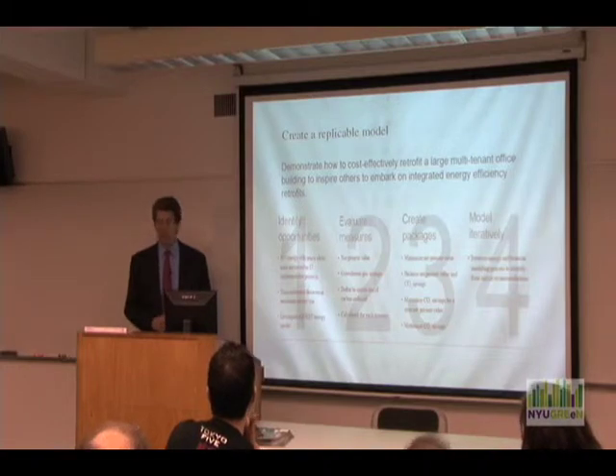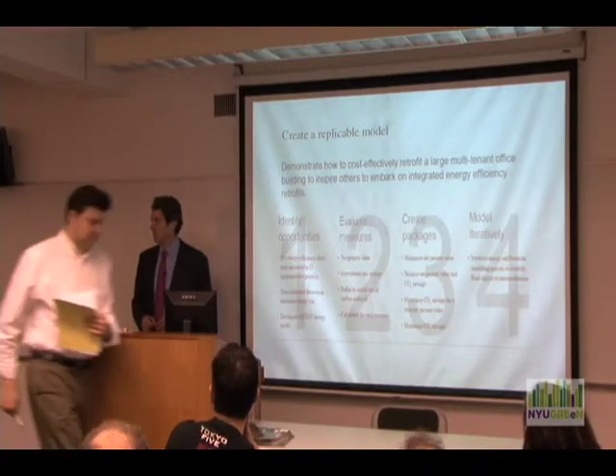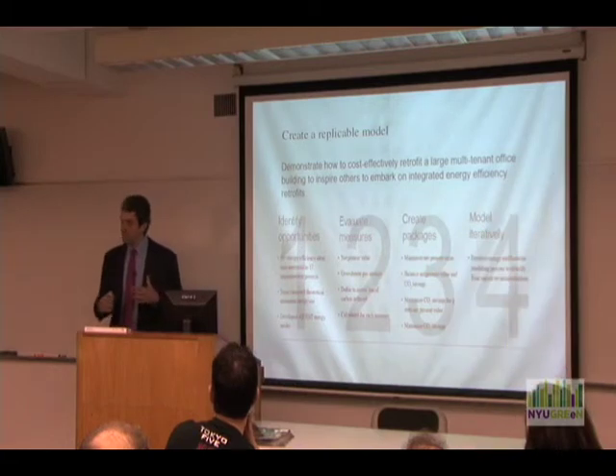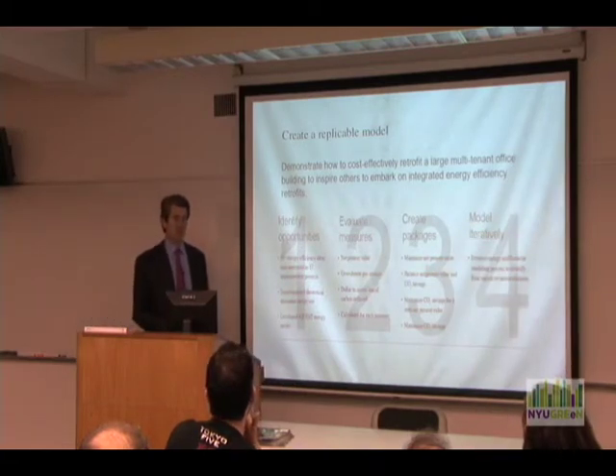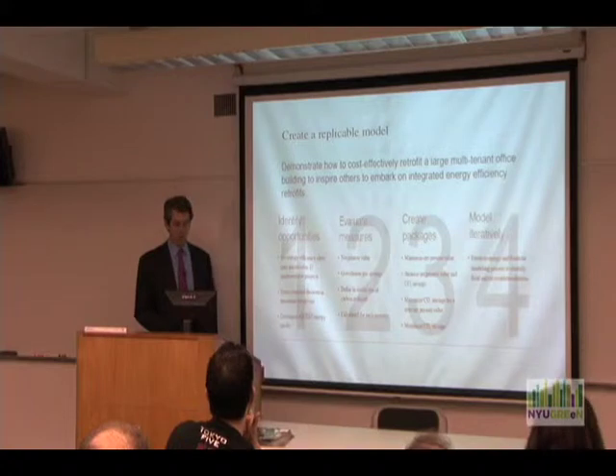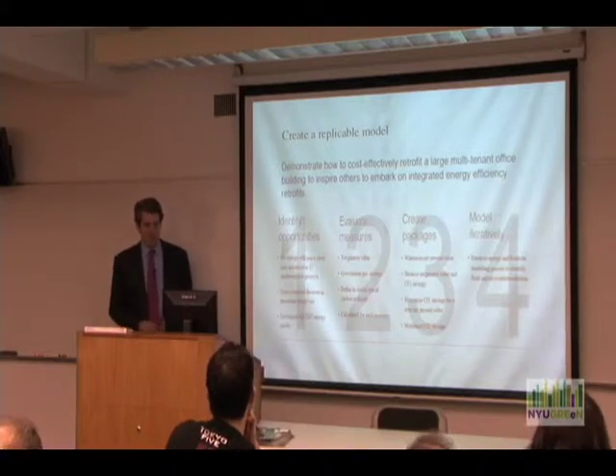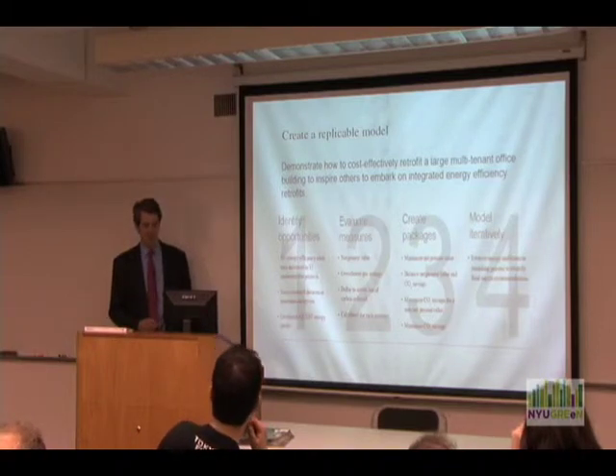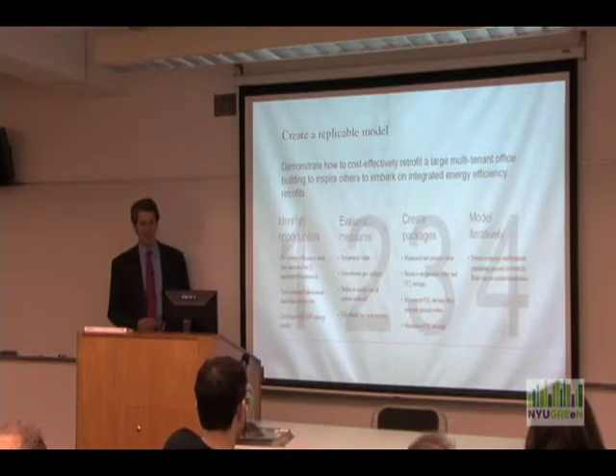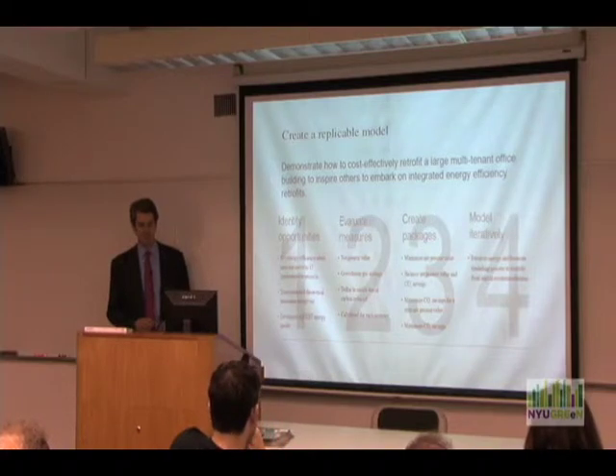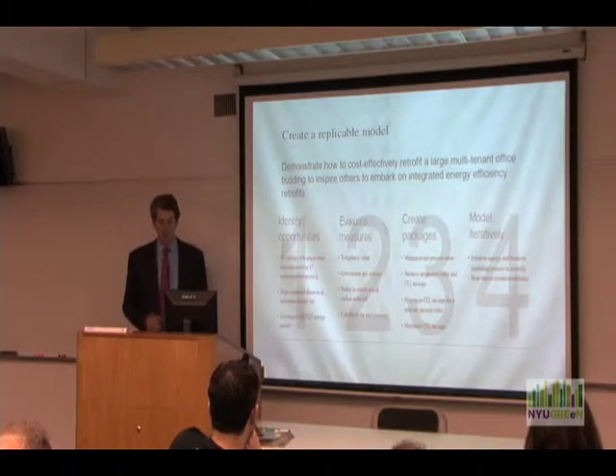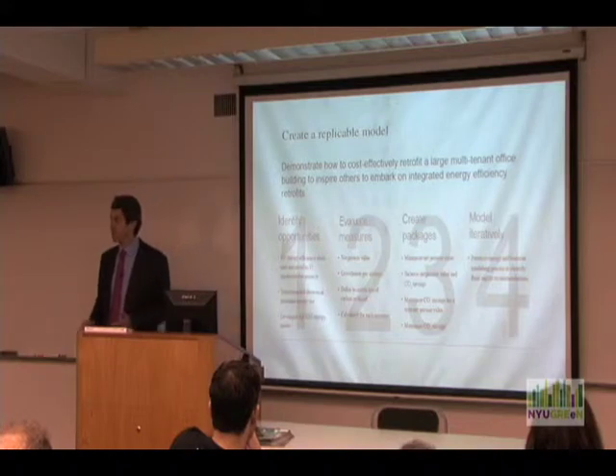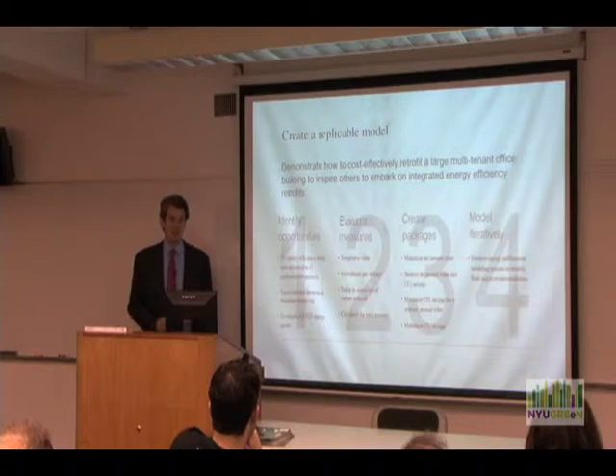Evaluating with this DOE eQuest system, in order to come up with the best permutation to produce the best result with the shortest term payback. So what we did, through the Rocky Mountain Institute, was develop what we called this theoretical minimum energy usage. However, as you'll see on the cost curve we put together, we could reduce energy consumption by about 60-some-odd percent, but the paybacks would be over an extraordinarily long period of time.